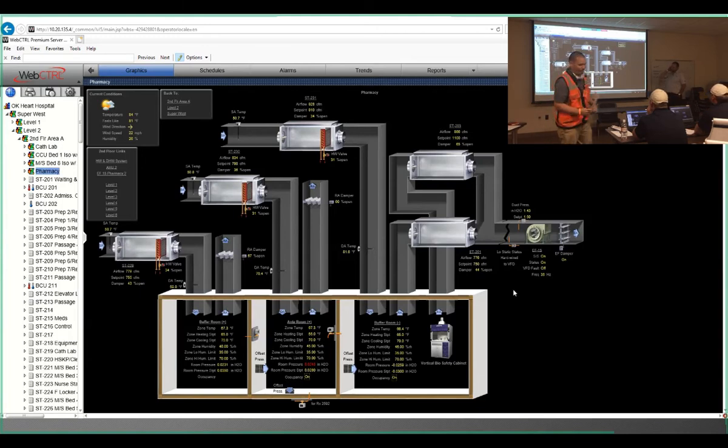But what Joe was talking about, agreed at this point: if somebody goes up to the air handling unit and leaves the door open on the return, those two labs are not going to alarm. It's just something on air handling units 3 and 4 on levels 2 and 3, which have the pharmacies. We have to have some return static right here. If the door on the return of the unit gets open or something happens on the return and we lose that pressure, you're going to get alarms on the pharmacy labs. A good example is a filter change, right?